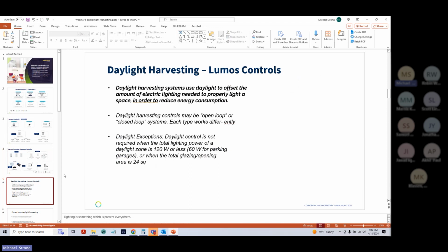So let's get to daylight harvesting and Lumos controls. As you're probably aware, I don't know how much everybody knows about daylight harvesting and why we do it. We use daylight to offset the amount of electrical or artificial light that we are powering within a facility, because they are near windows, typically showrooms, offices, conference rooms, break rooms, any place that is close to or has windows built in. Then there are going to be daylight zones, and more across the country. New York and California have already implemented, and on the West Coast in general, Oregon, Washington, California, New York, and most of the East Coast have implemented really strong energy codes that include daylight harvesting.